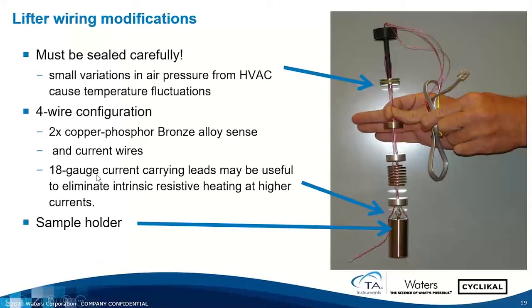In the past, and it may be useful for certain applications, we have used a thicker wire, a lower gauge, for carrying the current, to eliminate intrinsic resistive heating in the wire at higher currents. What I mean by that is, the 4-wire configuration can compensate for the voltage drop down the wires, but those wires are also going to carry current. And if your current is high enough, the wires themselves can start to produce thermal power, resulting in an extraneous source of thermal power that's not coming from your battery. And we'll show you how to determine that. And the sample, again, is placed inside the stainless steel ampule.